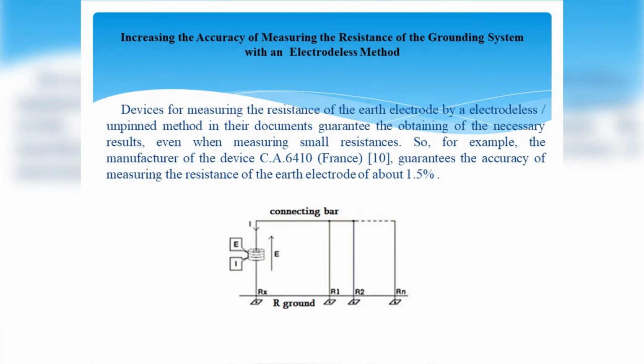In such cases, reckoning methods are used to determine the resistance of the GD. Given the known geometric dimensions of the ground contour under investigation and the known resistivity of the ground, these initial parameters are practically unknown, and therefore other methods and means of measuring the resistance of the ground are needed, independent of geometric dimensions of the grounding loop and the resistivity of the ground: electrodeless unpinned methods. This method excludes the placement of auxiliary electrodes in the ground, greatly shortens the measurement time, and is often the only possible one.